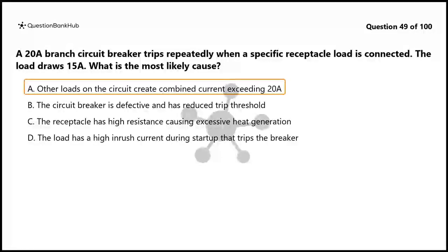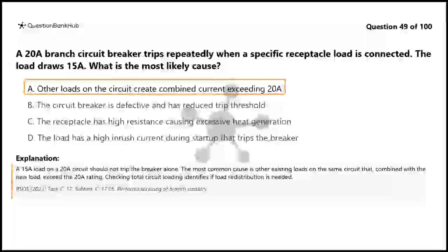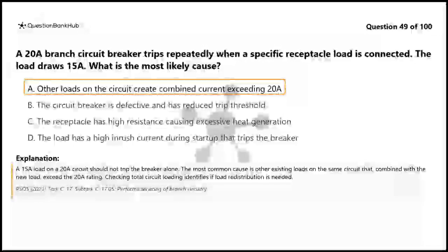The correct answer is A. Other loads on the circuit create combined current exceeding 20 amps. A 15 amp load on a 20 amp circuit should not trip the breaker alone. The most common cause is other existing loads on the same circuit that, combined with the new load, exceed the 20 amp rating. Checking total circuit loading identifies if load redistribution is needed.